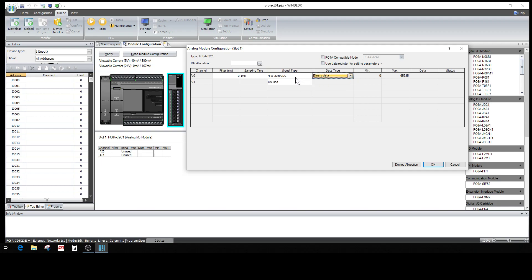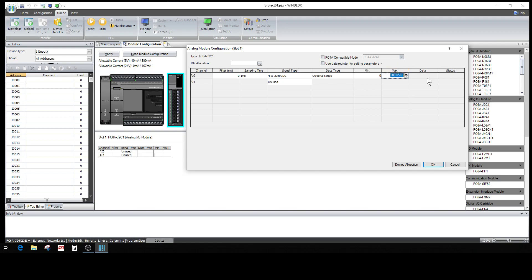Here you can use binary data, or you can do an optional range. For example, if you have something with a temperature range of zero to 500 degrees, it'll actually show zero to 500 degrees. Or you can leave it at four to twenty and leave it binary just like it is, and it'll have the scale for whatever you're using.